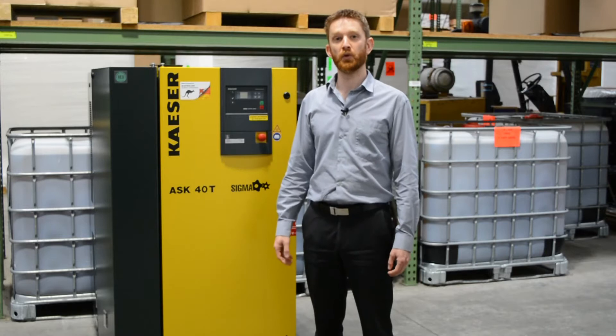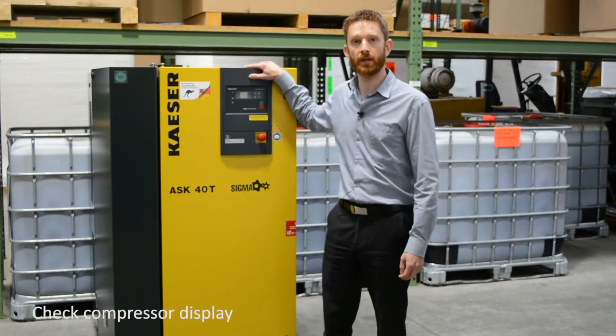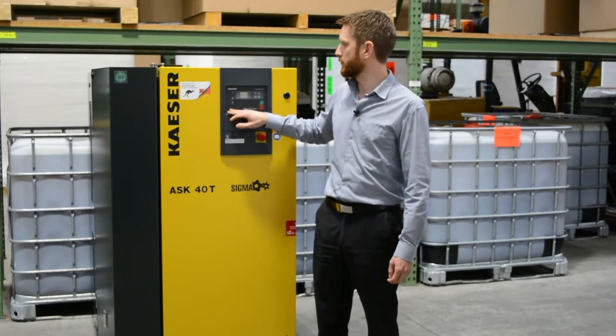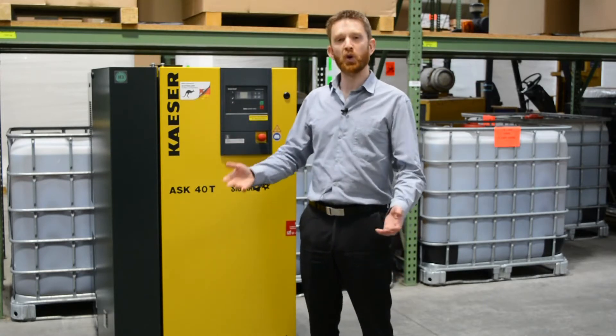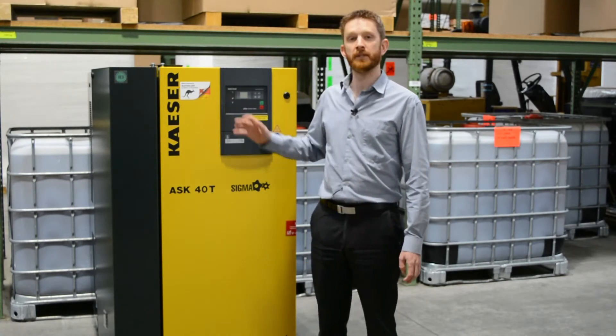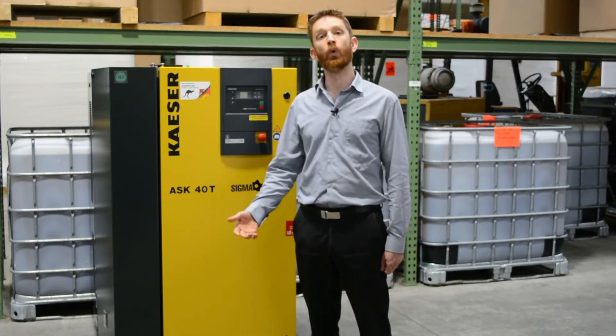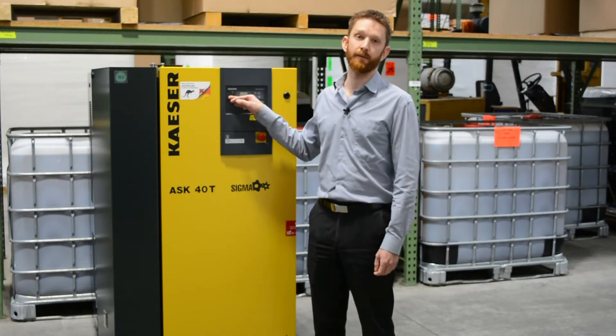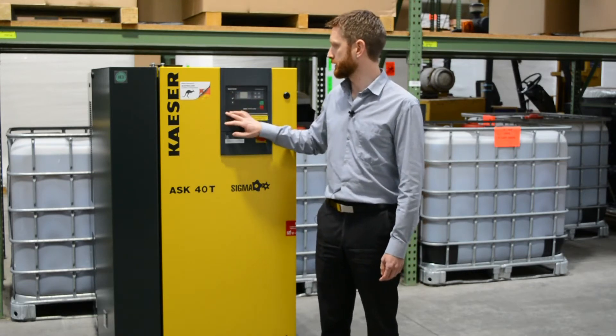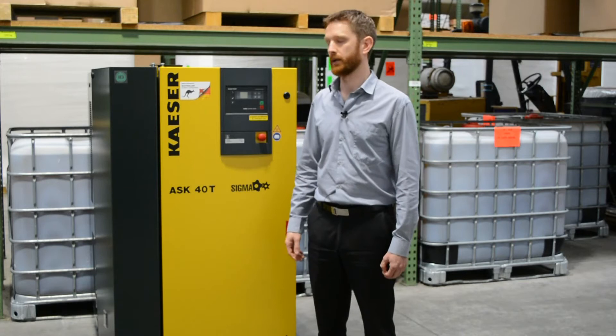For daily checks, you probably want to glance at the controller. Most compressors like this have some sort of smart controller on them, and the Kaeser in particular has a traffic light system on the controller. If there's no lights or a green light, that means it's healthy. If there's an amber or orange light, it means there's a warning — it could be due for a service or getting a bit warm. If there's a red light, that means there's an alarm and something urgently needs attention. You can also check the display — it'll flag if it's due for maintenance and you can see the oil temperature.